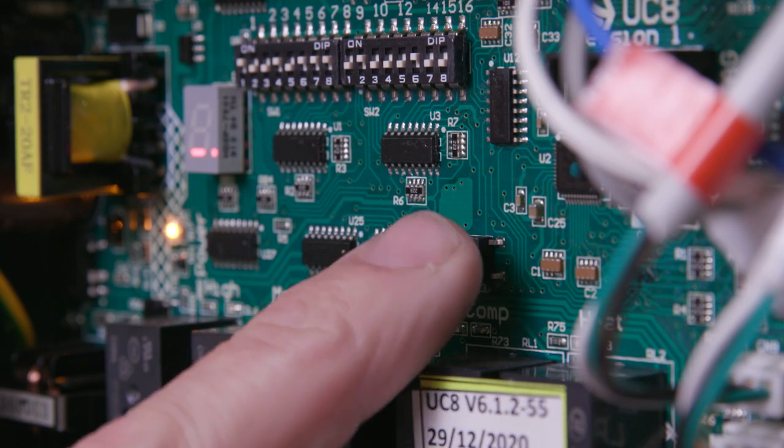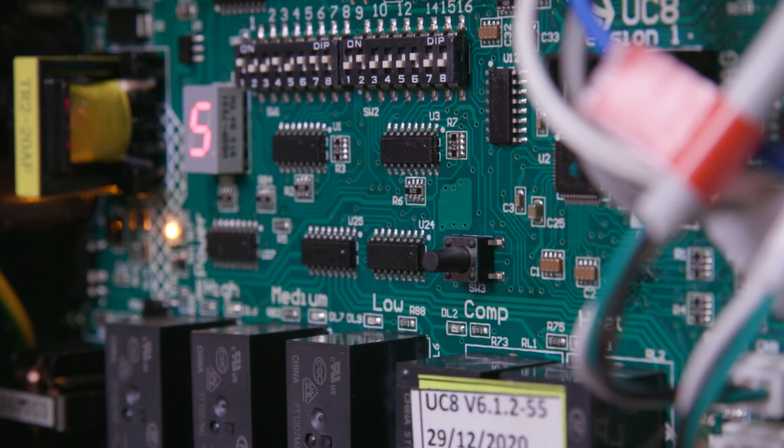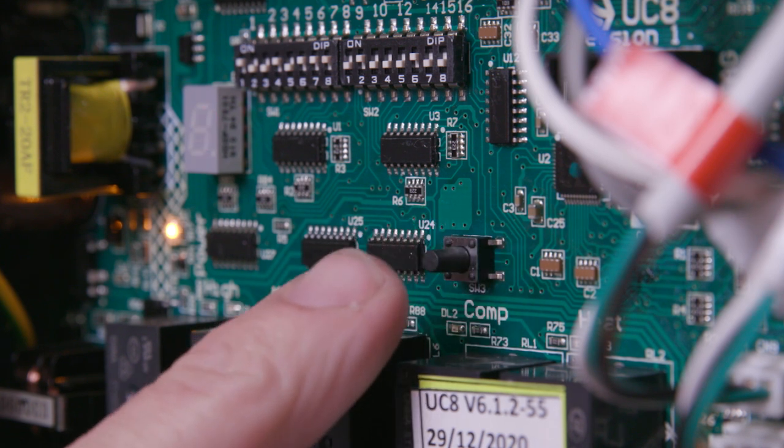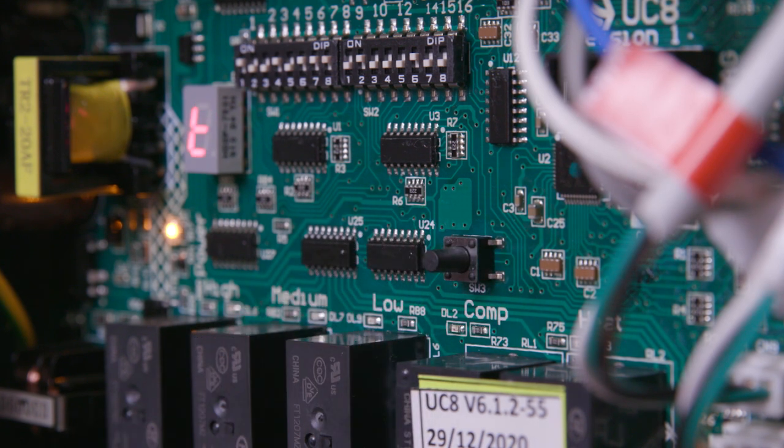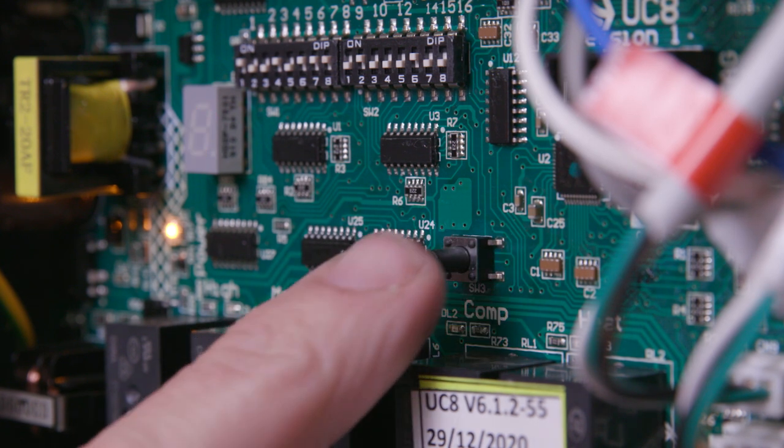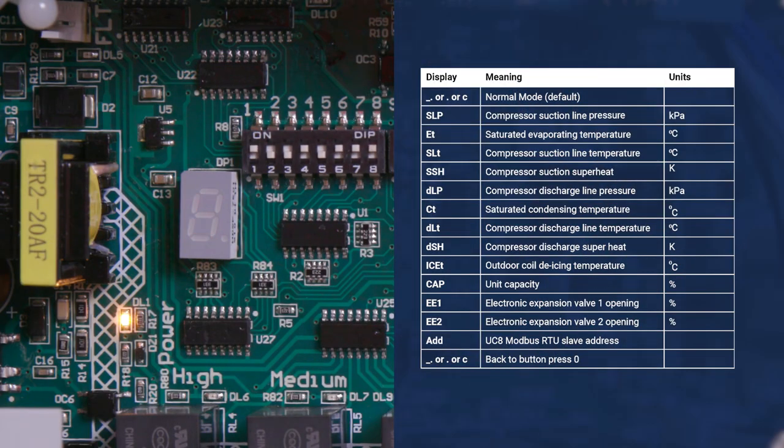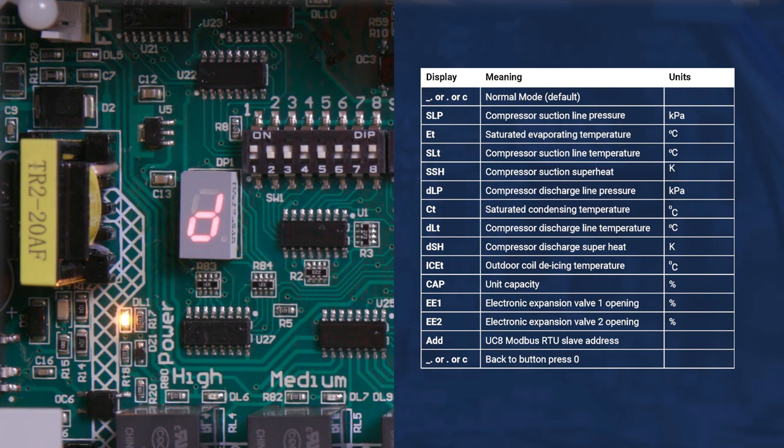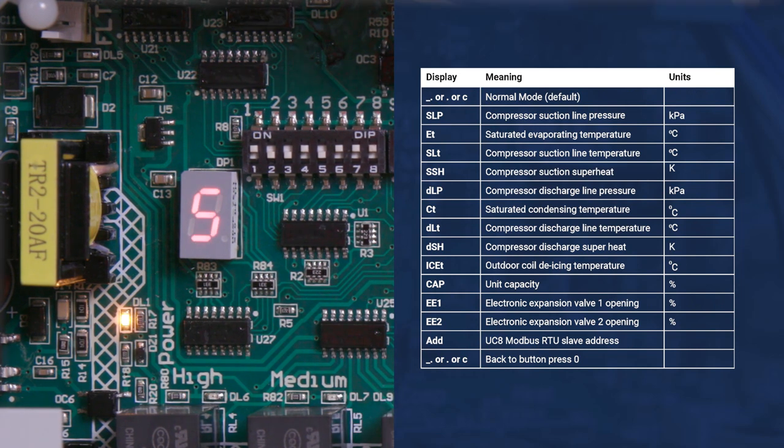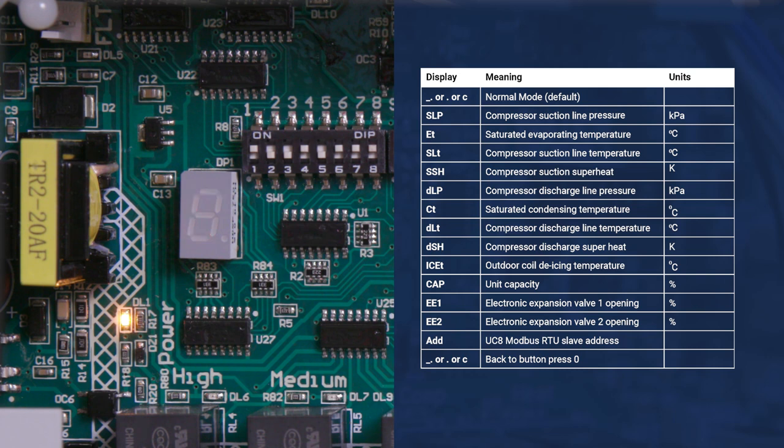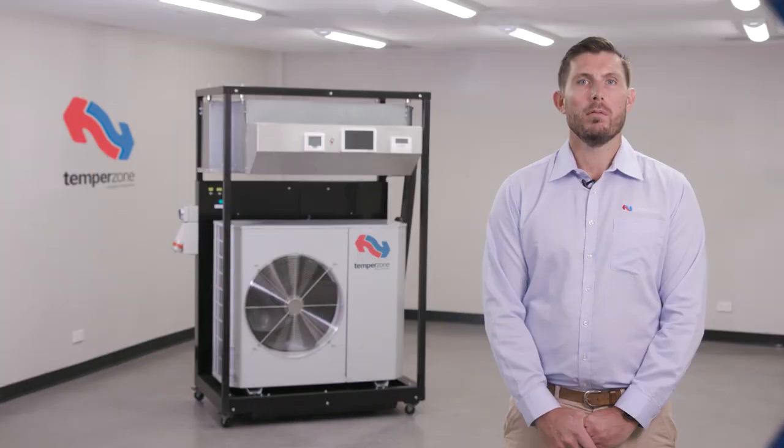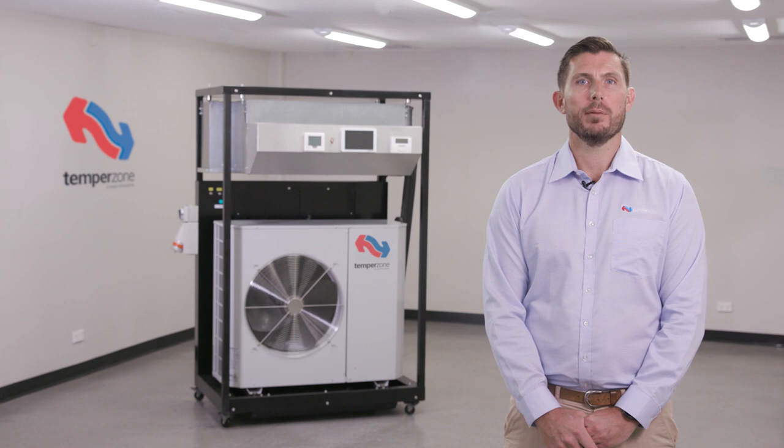Tapping of the SW3 push button will display critical operational information of the system on the UC8 LCD screen, including suction pressure, discharge pressure, superheat, capacity, and more. Reference to this information can be found in the document case within the electrical compartment or on the electrical panel itself.